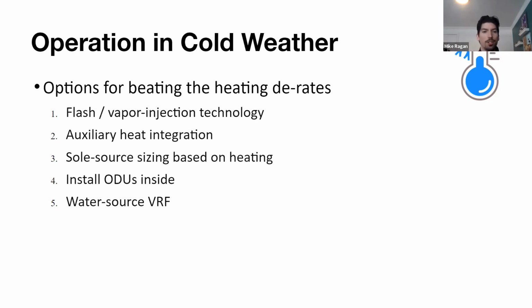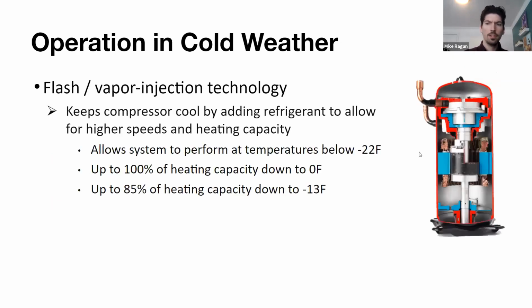So the different ways that we approach this are as follows. The flash or vapor injection technology that has allowed for more extended heating temperatures that we can operate in, tying in those auxiliary heat sources, how to design VRF as the sole source. If you want to install your outdoor units inside, that's a way of avoiding some derates as well, as is water source, just eliminating the ambient conditions altogether. So first off, I want to talk about our flash or vapor injection technology. Again, going back to the proprietary terms, Mitsubishi has our Hyper-Heat equipment, Daikin has the Aurora line of equipment. Those are the cold climate technology series of equipment that allows for extended performance in cold temperatures.